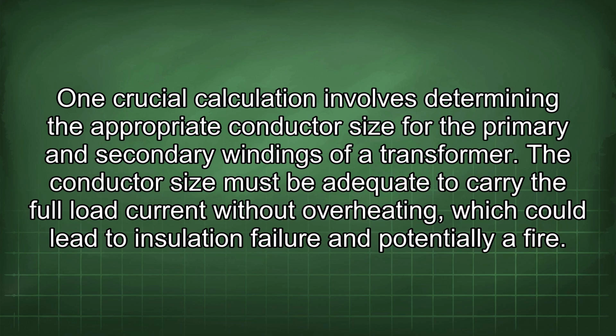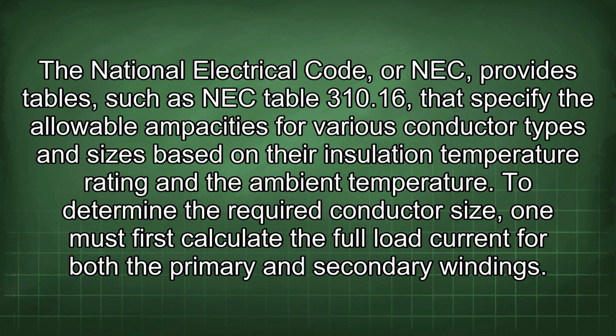One crucial calculation involves determining the appropriate conductor size for the primary and secondary windings of a transformer. The conductor size must be adequate to carry the full load current without overheating, which could lead to insulation failure and potentially a fire. The National Electrical Code, or NEC, provides tables, such as NEC Table 310.16, that specify the allowable ampacities for various conductor types and sizes based on their insulation temperature rating and the ambient temperature.